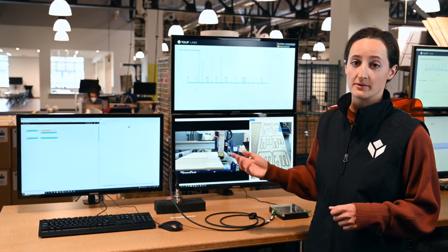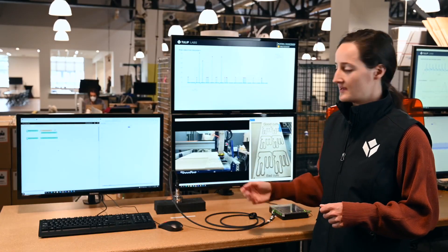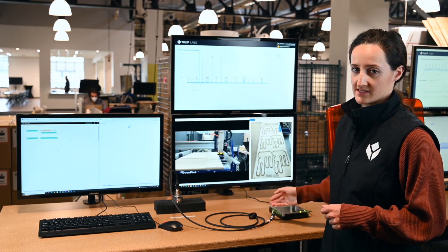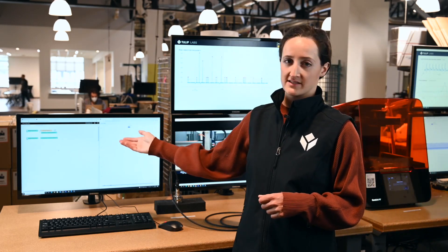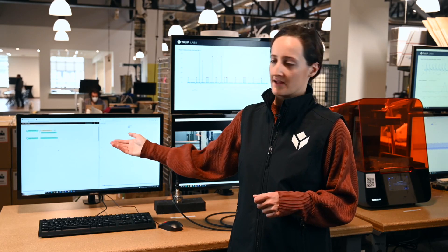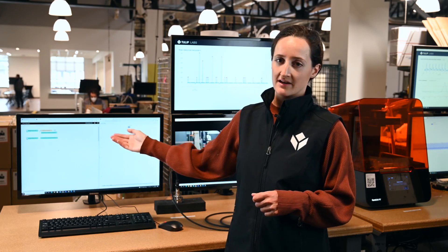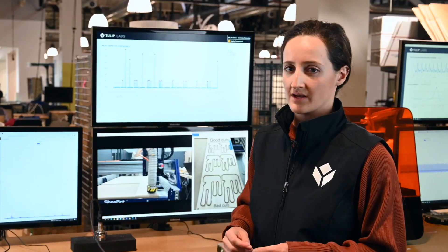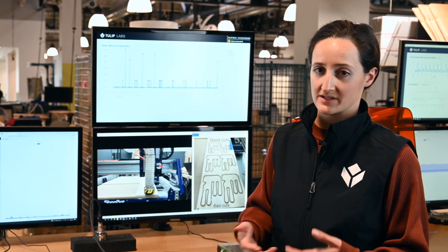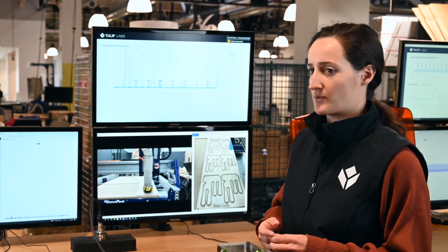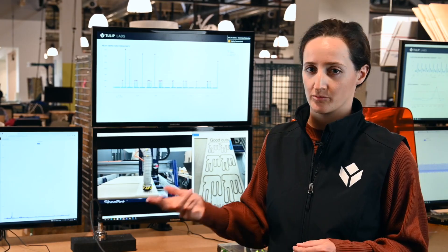So this data path is going through Node-RED. The Edge.io is reading the inputs into its analog port, and then in Node-RED, we're processing the data and finding the peak frequency of the analog data, which is being sampled at eight kilohertz, so relatively high frequency. So in this example, we're showing how Edge.io can monitor vibration or similar sensors to detect whether a machine is performing well or poorly.